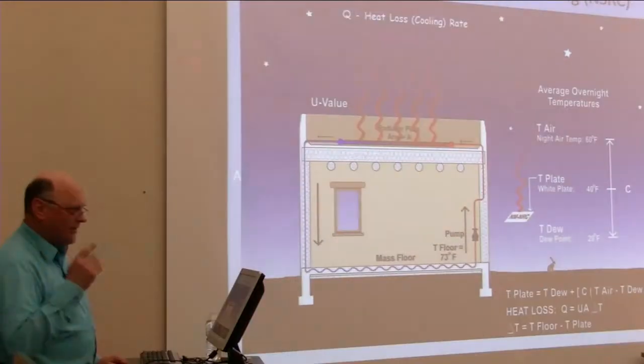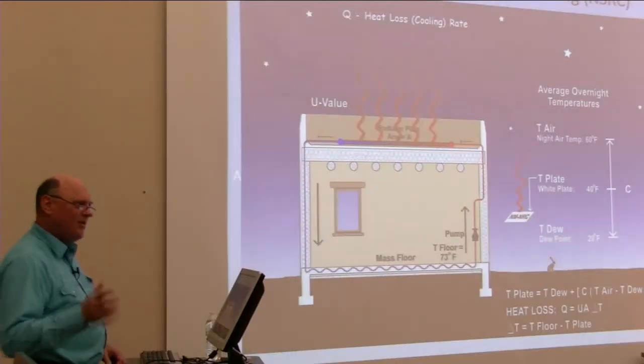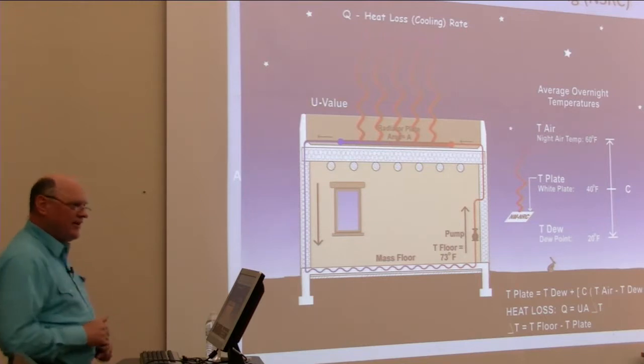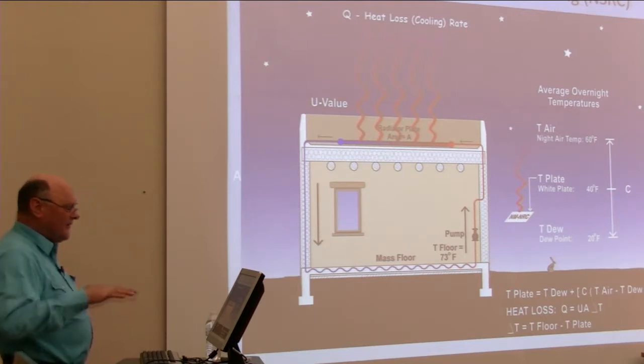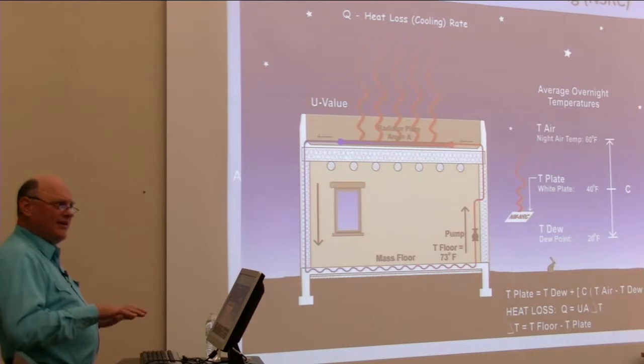And that's what happens here with night sky radiant cooling, especially in this climate. On a clear night, you can expect the plate temperature to be much colder than the air temperature. And when the plate temperature drops to a nice cooling temperature, you can pump fluid through it and cool the fluid and pump that cool fluid through your floors. You can do it all night for about 10 hours of cooling your floors if you want to. And then your floors are much cooler than normal the next day.